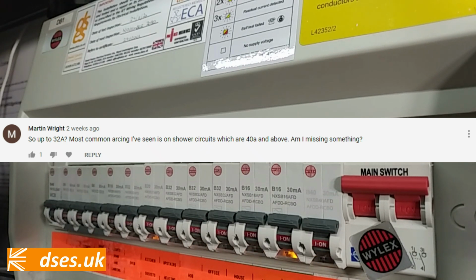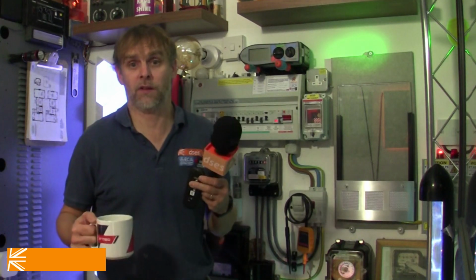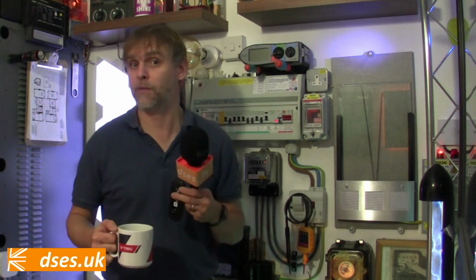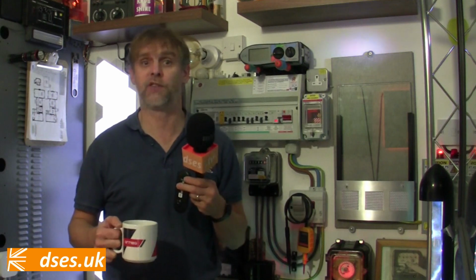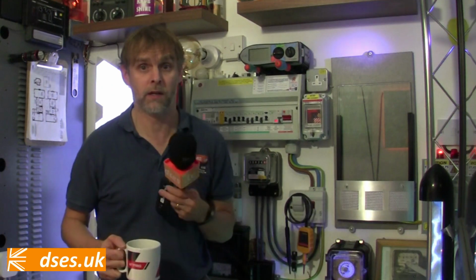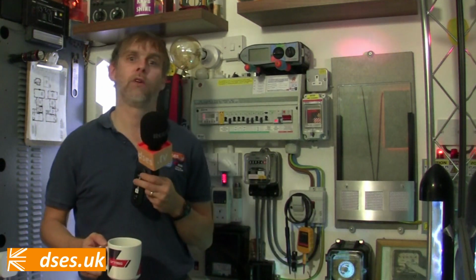Am I missing something? Well, we both must be, Martin, as I don't know why the draft changes for circuits at 32 amps or below when it's 40 amp showers and cookers that see the most thermal damage from poor connections in my experience. AFD devices need a good couple of amps to operate, so a loose connection on your LED lighting will persist all day long without the fucker tripping. It would make more sense to recommend them on circuits of 16 amps or above.